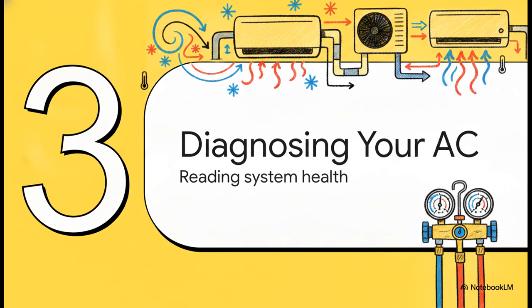All right, part three, diagnosing your AC system. Let's see how professionals actually read your system's health. Monitoring the relationship between all these temperatures is basically the ultimate diagnostic tool. In a perfect, ideal state, your room's return air pulls in at around 24 to 26 degrees Celsius. The discharge air blowing out is a crisp 16 degrees. That means you've got a perfectly healthy 8 to 10 degree temperature drop. And underneath it all, the internal coil is sitting safely at 6 degrees Celsius. If you see these numbers, your status is absolutely perfect. The system is efficiently absorbing heat and removing humidity with zero risk of freezing.